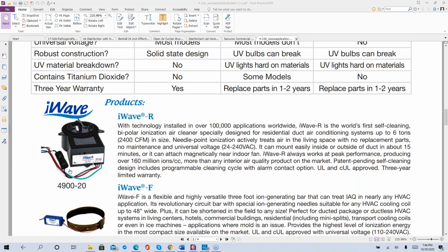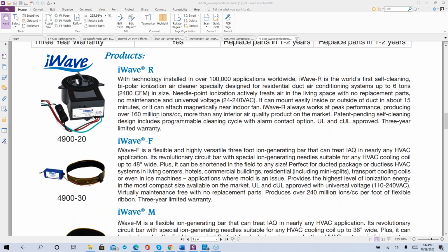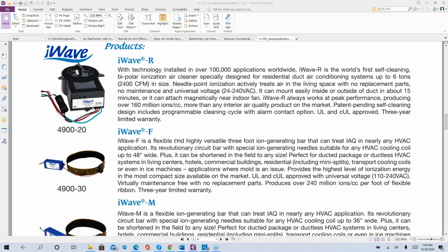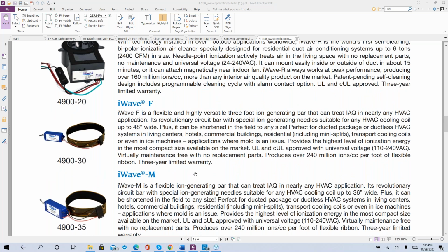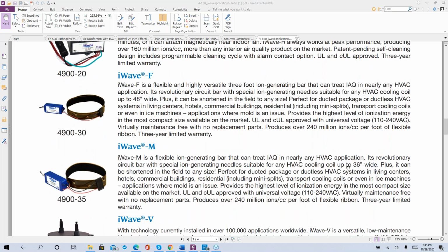So the R is the prevalent one that has upwards of 6 tons of airflow, or 2,400 CFM. And so that's a lot of millions of ions. And the iWave F and the iWave M, these are the flexible ion generating bars. They're more like a belt. This one is 36 inches wide, and this one is 48 inches wide. These can be installed in ductless split systems, Mitsubishi's, Sanyo's, anything that you want. They can also be installed in small tonnage fan coils. And again, put them between the filter and the coil, and it cleans the coil as well as flows out into the airstream and does their damage to the pathogens as well.